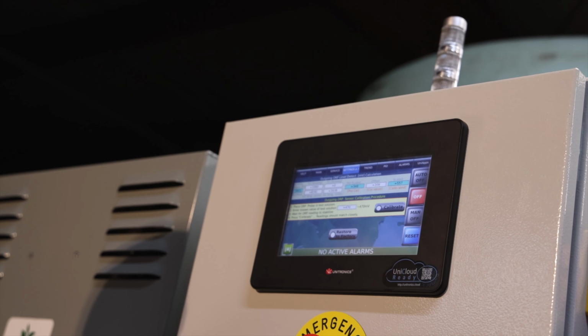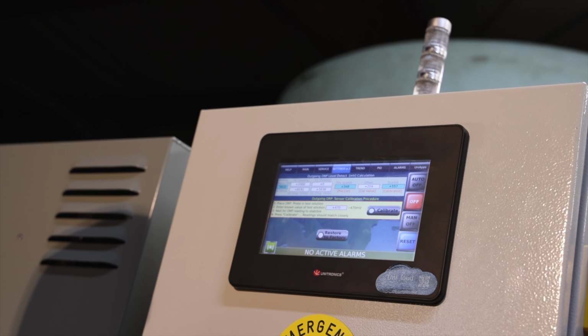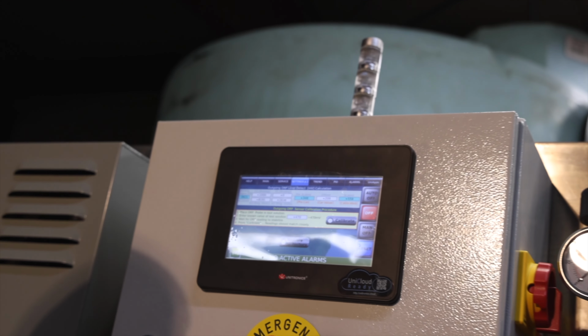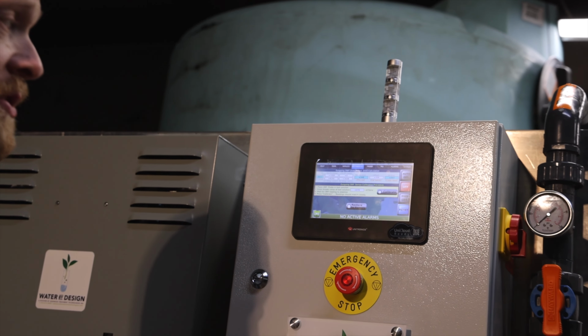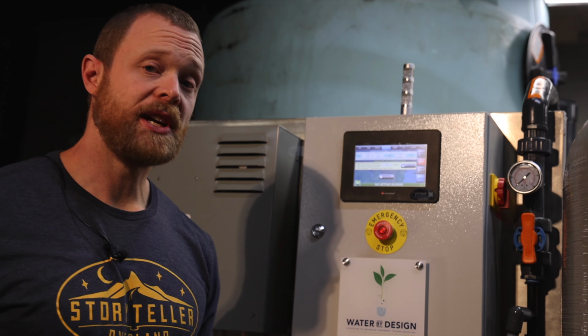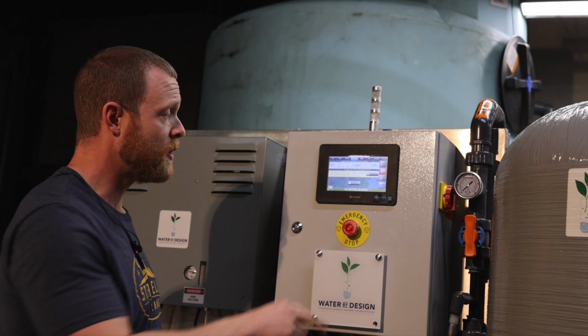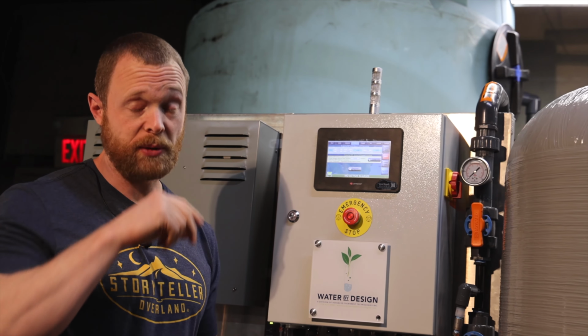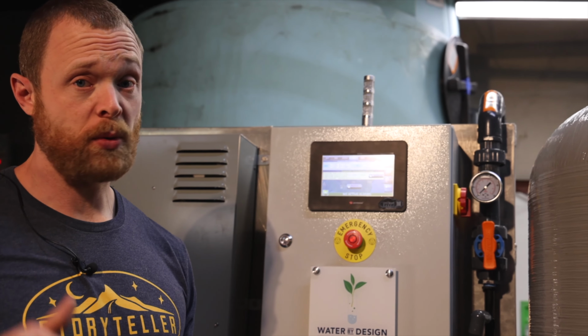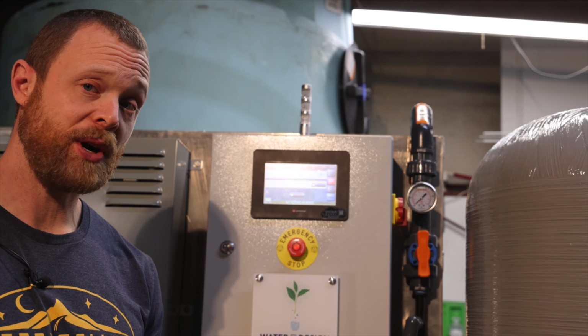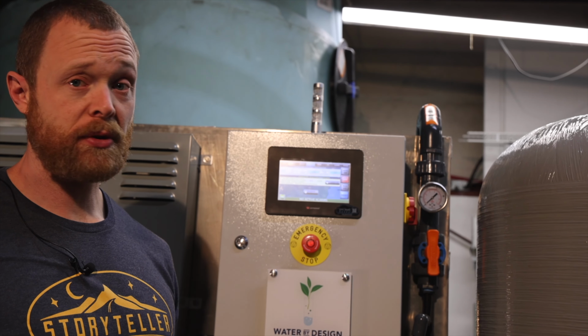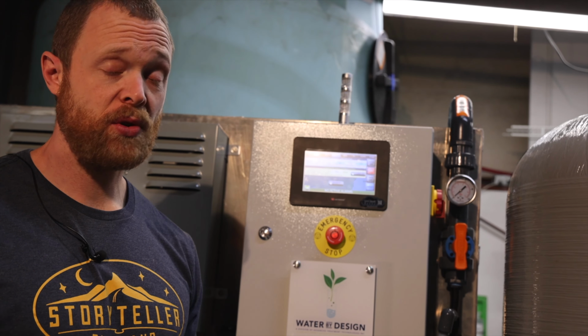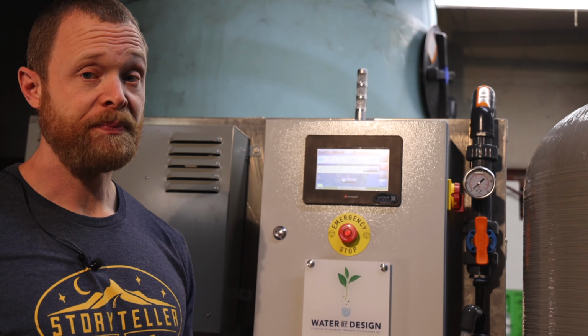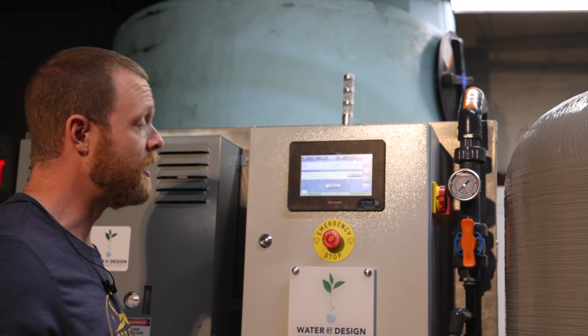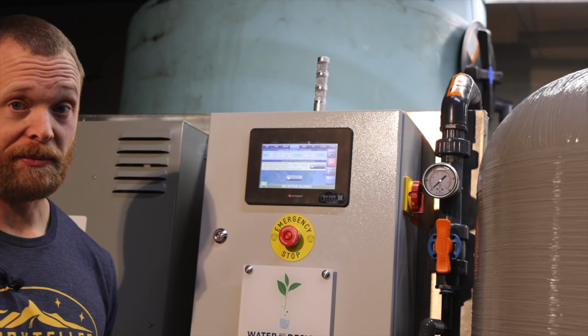After you've removed the probe, you're going to place the tip in the calibration solution that we provide for you. If you need some extra, you can let us know. We'll send it to you. The most important thing here is that you allow that value to stabilize. So the place where it shows you what the probe is currently reading, that's going to fluctuate for a little bit when you put the tip in that calibration solution. This may take 2, 3, 4 minutes, but you need to make sure that that reading stabilizes. And after it does, and only then, will you come up here and push that calibrate button.